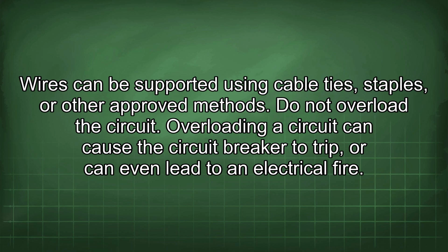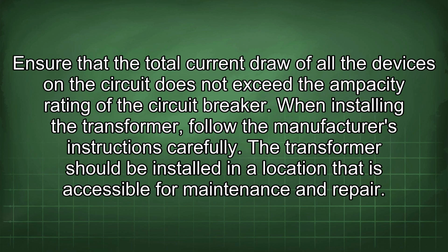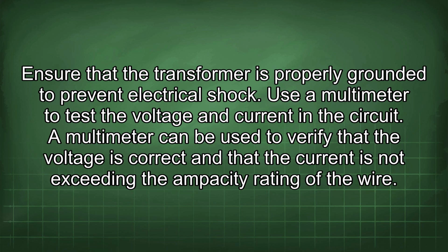Do not overload the circuit. Overloading a circuit can cause the circuit breaker to trip, or can even lead to an electrical fire. Ensure that the total current draw of all the devices on the circuit does not exceed the ampacity rating of the circuit breaker. When installing the transformer, follow the manufacturer's instructions carefully. The transformer should be installed in a location that is accessible for maintenance and repair. Ensure that the transformer is properly grounded to prevent electrical shock.